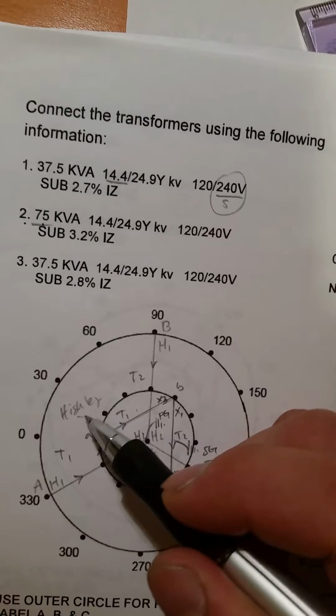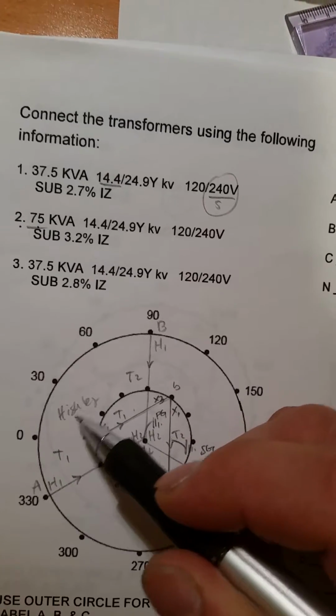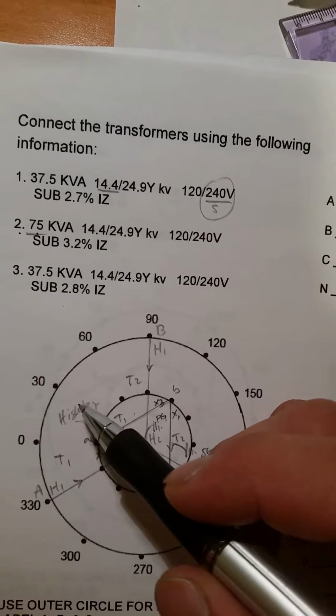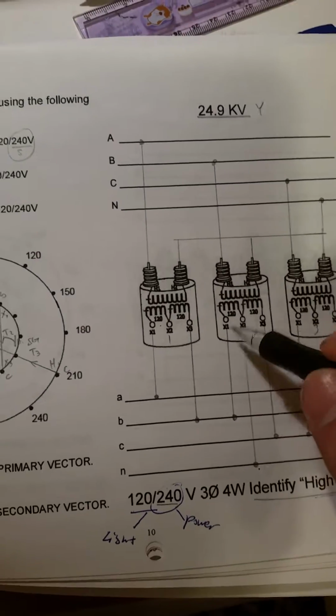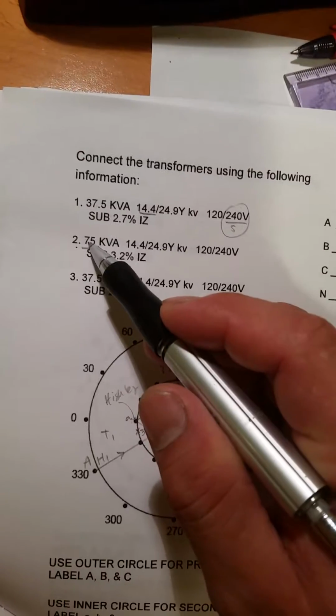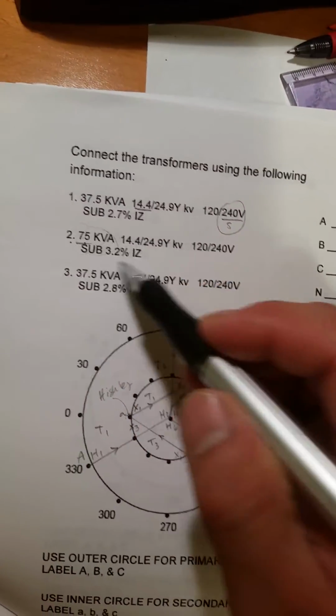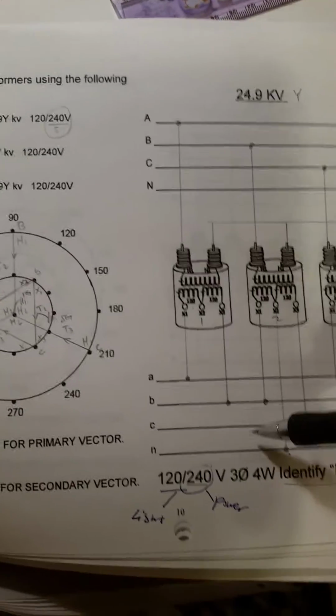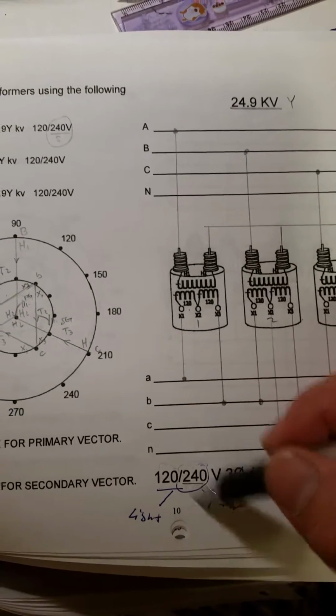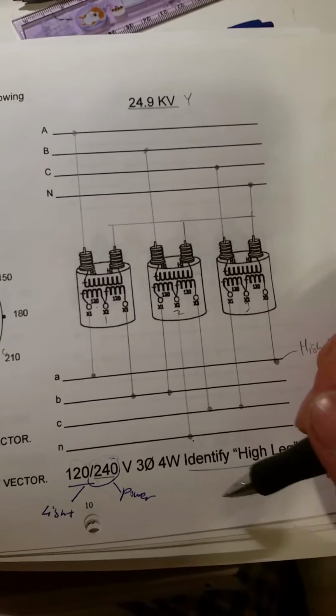The high leg is usually marked with orange tape out in the field. The reason why I chose to ground this transformer 2 is because it has a 75 kVA can - it's bigger, so it's using it for the 120 light and 240 3-phase bank for the power.